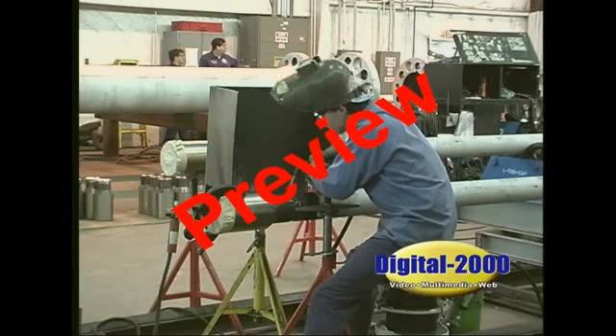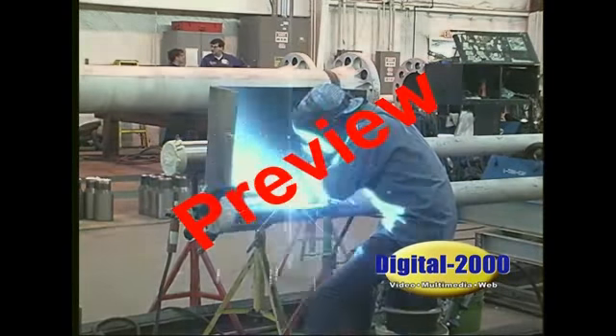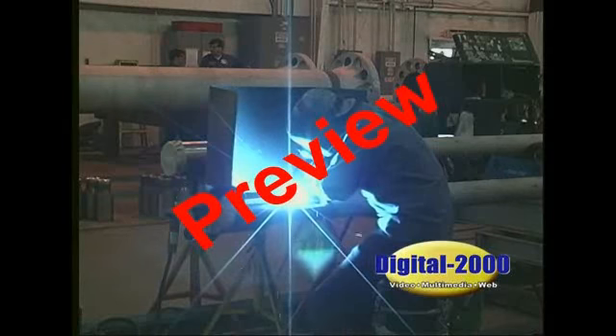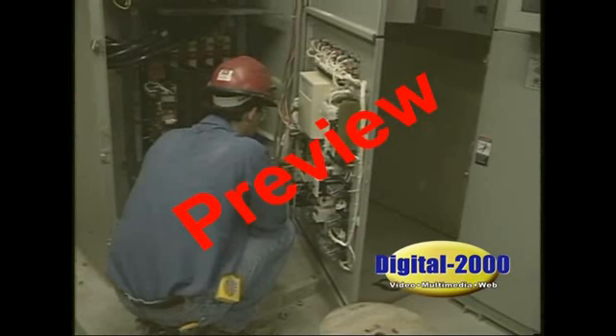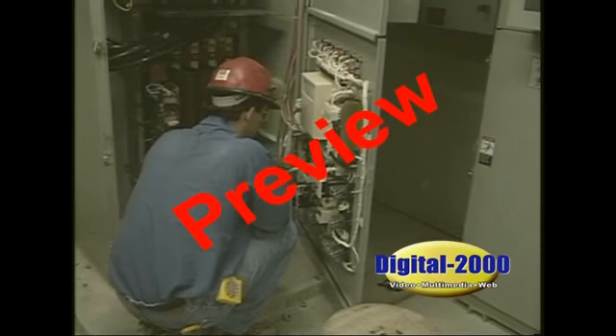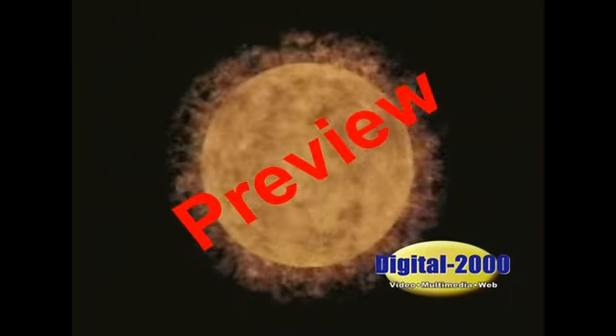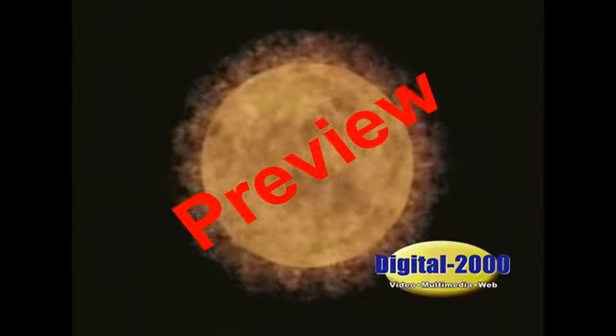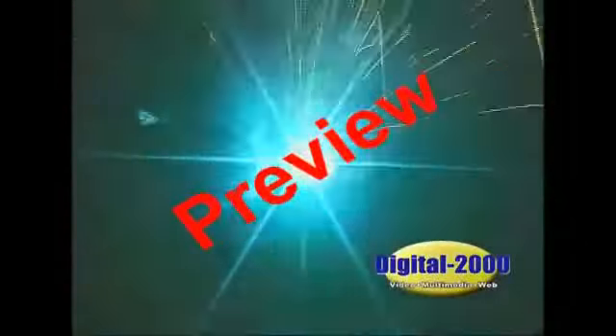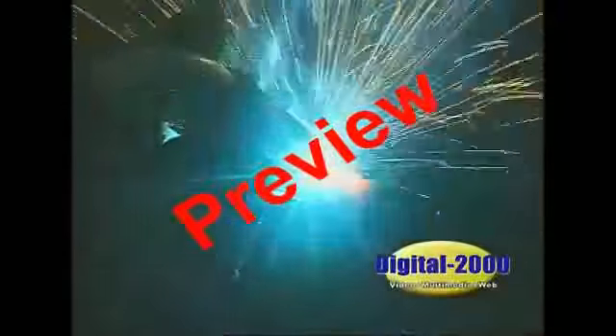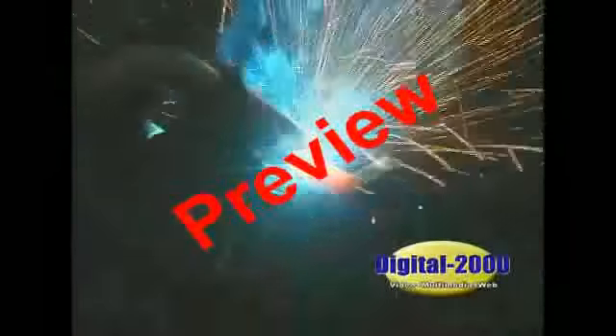When electric current flows between two or more separated energized conducting surfaces, an arc occurs. Some arcs are intentional, such as arc welding, or they may be accidental, caused by a tool touching a probe to the wrong surface. One common cause of arcs is insulation failure. Temperatures at the arc terminals can reach or exceed 35,000 degrees Fahrenheit, or 4 times the temperature of the sun's surface. The heat energy and intense light at the point of the arc is termed arc flash. Air surrounding the arc is instantly heated and conductors are vaporized, causing a pressure wave termed arc blast. It's more like an explosion.